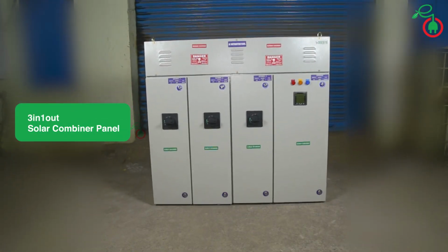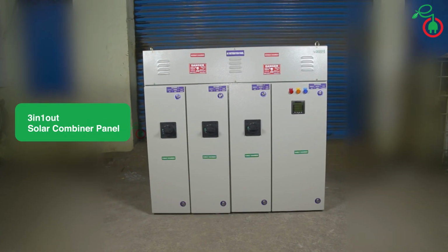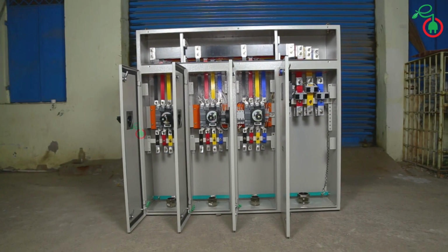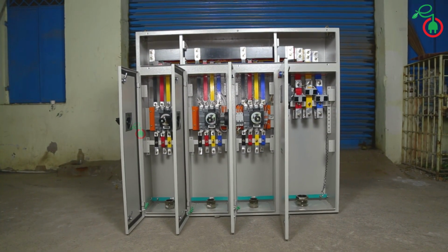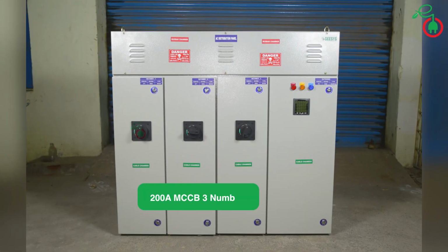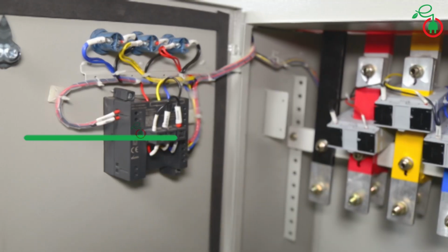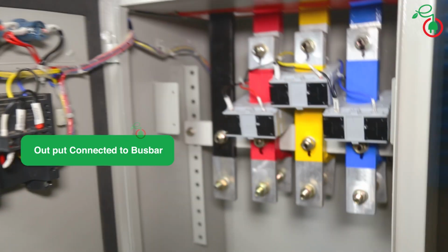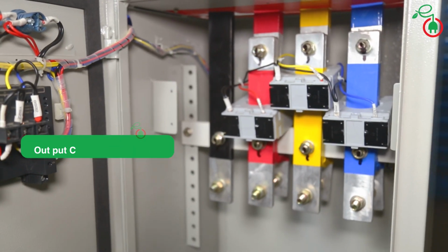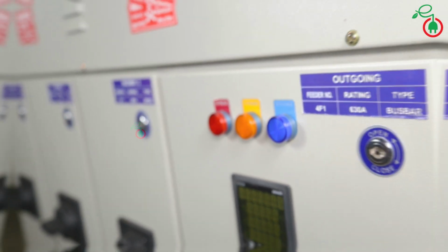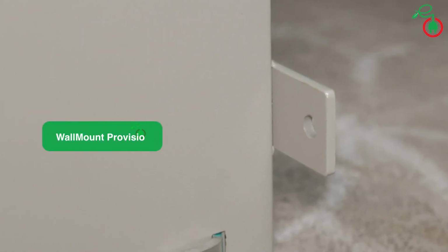GEESYS recently manufactured a 3-in-1 out solar AC combiner panel, a solar combiner box suitable for a 300 kW solar power plant. Here on this panel, GEESYS has used 200 amps MCCB, 3 numbers, and the output 600 amps cables are connected directly to the busbar. The panel is specially made as the indoor horizontal type. The panel has been made with wall mounting provisions.